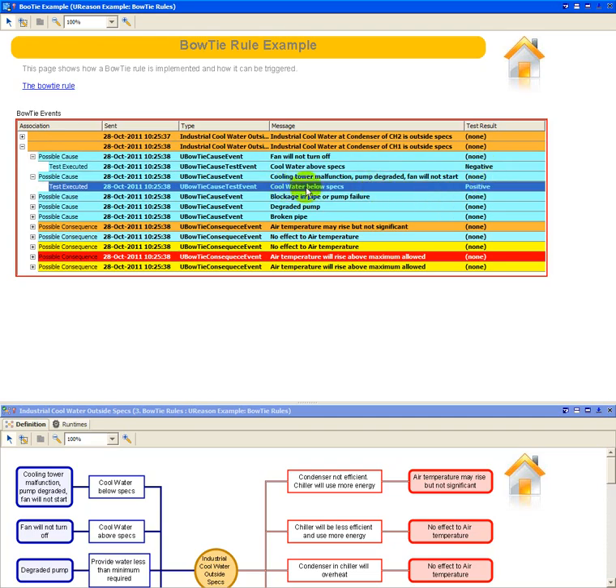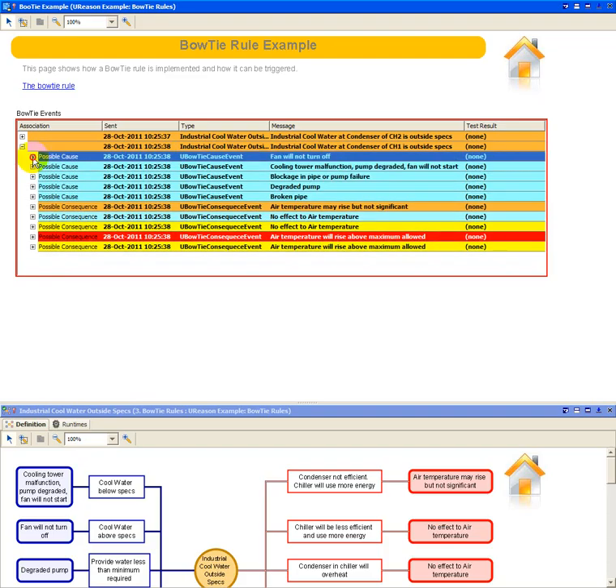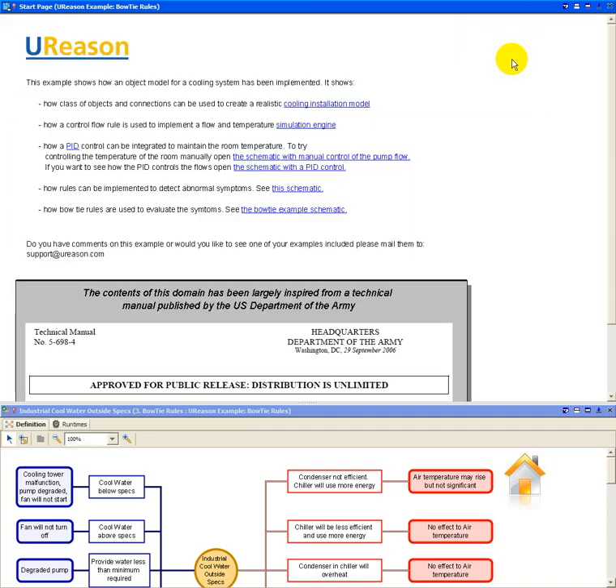And I can click on each possible cause and see whether the test was evaluated positively or negatively. In this case, the real cause of this event is the fact that the temperature was below the specification. This test is positive. And once the rule has executed all the causes, it will try to determine which are the possible consequences and assign to each of them a different color, a different priority. So for instance, in this case, this one here has the highest priority and the highest likelihood. And this closes the demonstration. Thank you for watching.